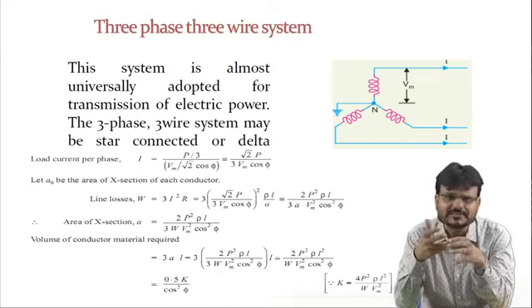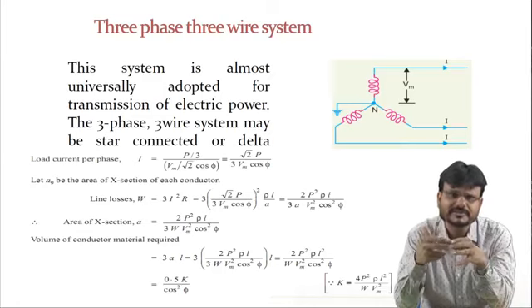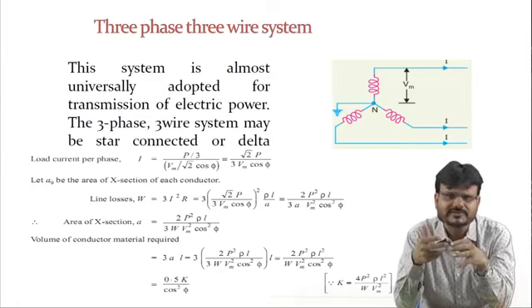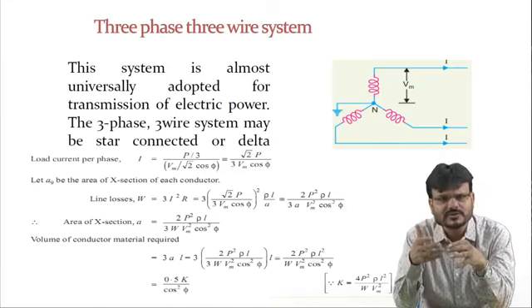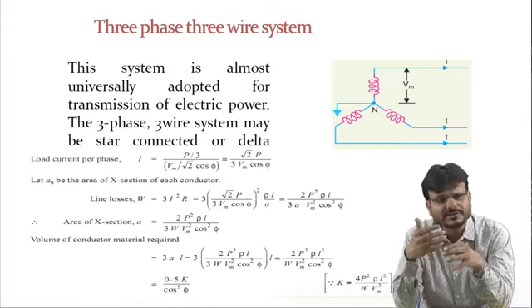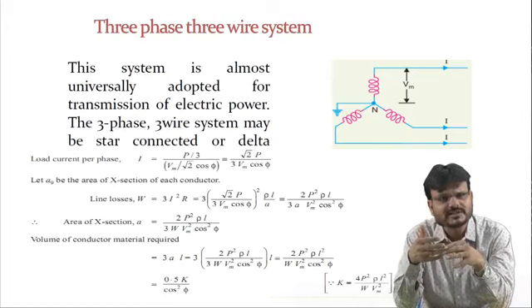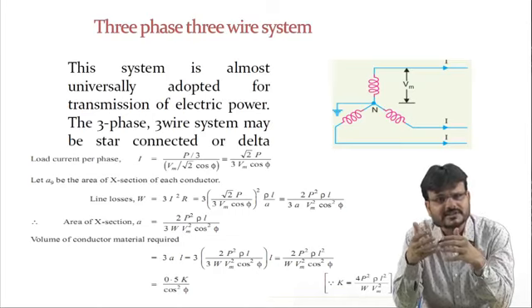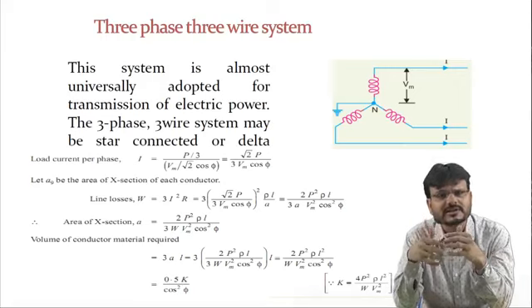That means of course this value will be less than the DC two-wire system. So if you transmit the same amount of power with a three-phase three-wire system, you are able to save the volume of conductor material required. Saving volume means the cost of conductor material is less, making it very economical. So AC transmission with three-phase three-wire system is advantageous in terms of money and in terms of the weight and volume of conductor material required.